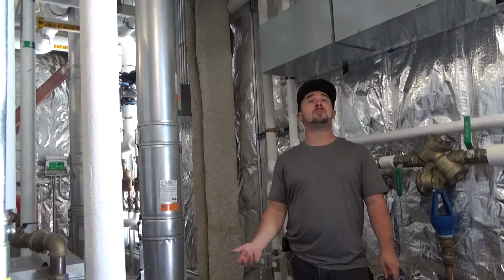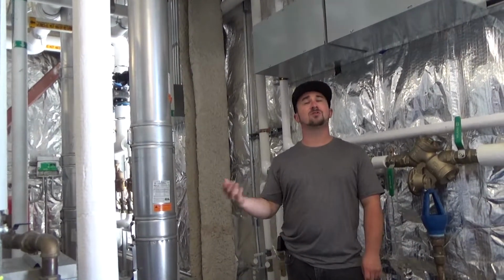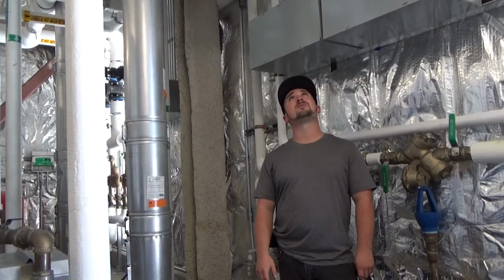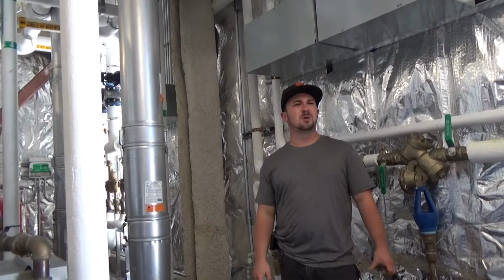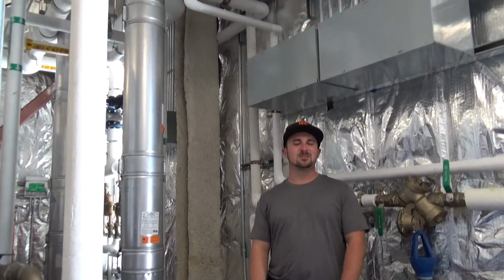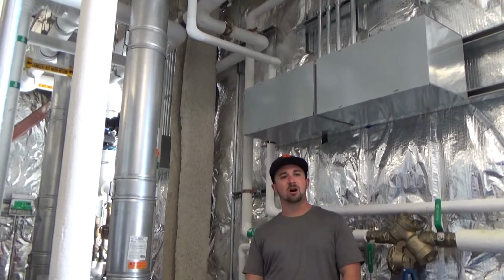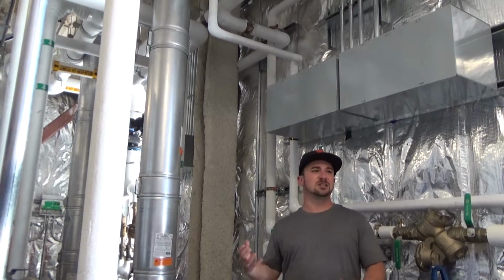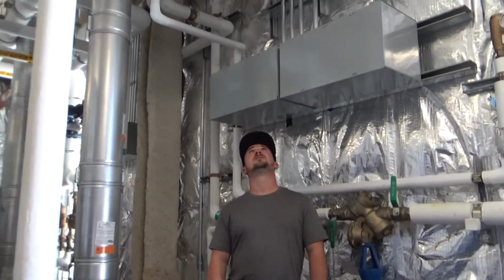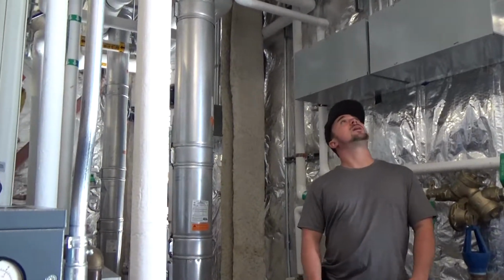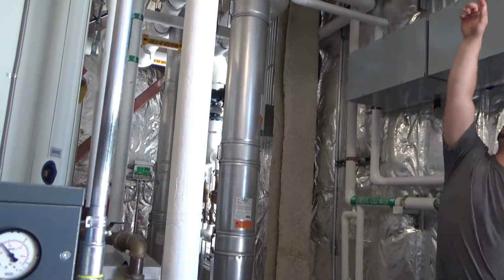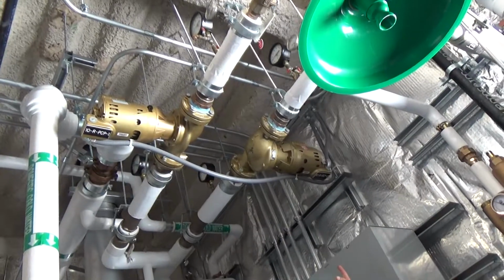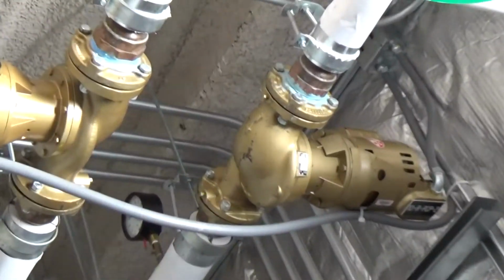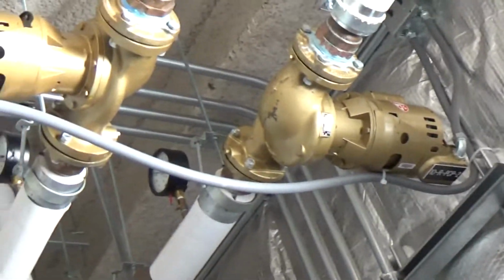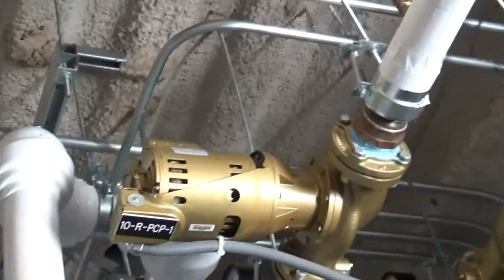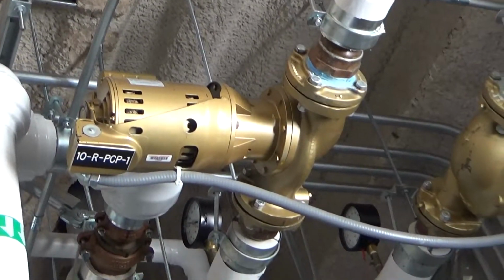You are going to build up crud every once in a while over time. So it's good to go through and clean it out so the motor doesn't get stressed. If you start stressing out the motor, it's not going to live as long. So it's good to keep that thing nice and clear, with no obstruction and no stress on that motor. So the nameplate is that little bad boy right there. That's for the whole pump itself. And the motor also has a sticker located on the top, so that'll give you all the motor information.